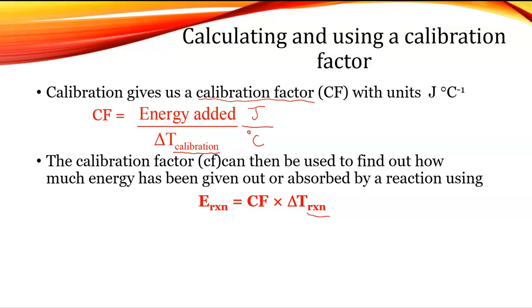Very frustrating, very confusing. So 1 delta T was during calibration. And you work out the calibration factor by dividing the energy added. So that was your V times I times T. And then this one is delta T cal. So VIT over delta T of calibration gives you the calibration factor.